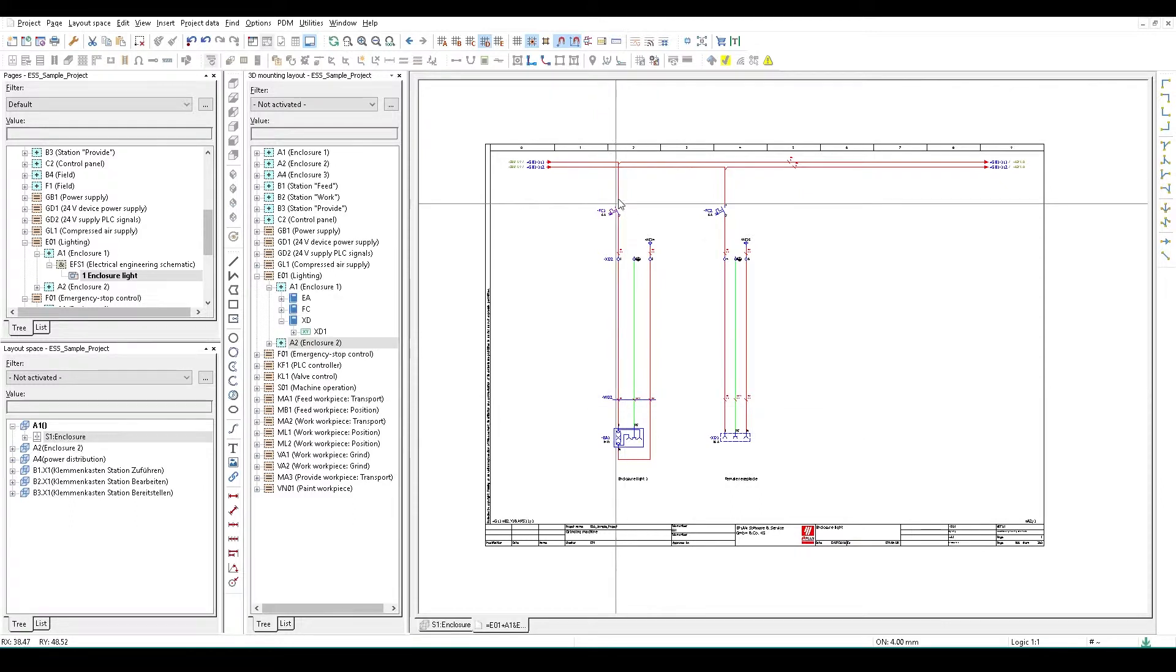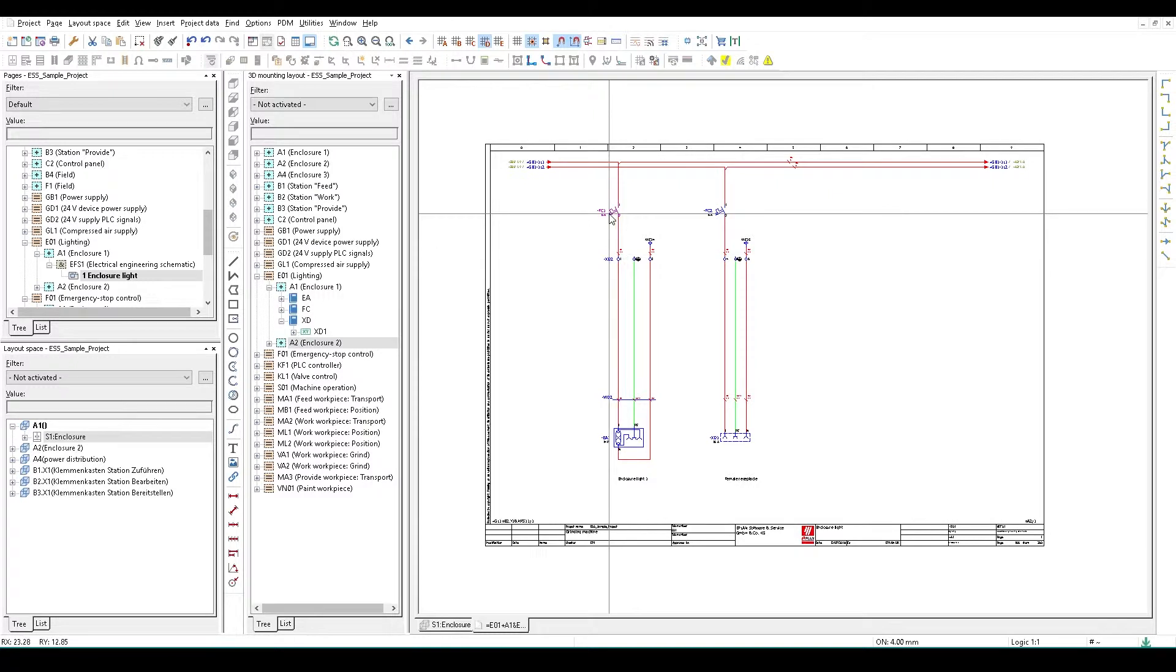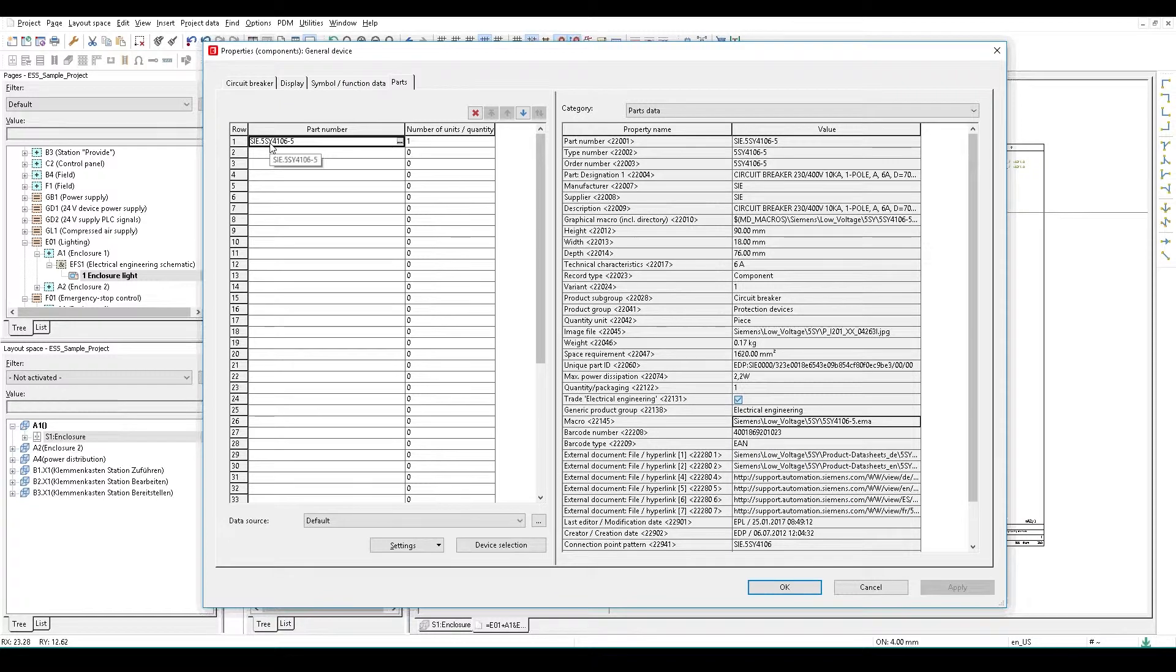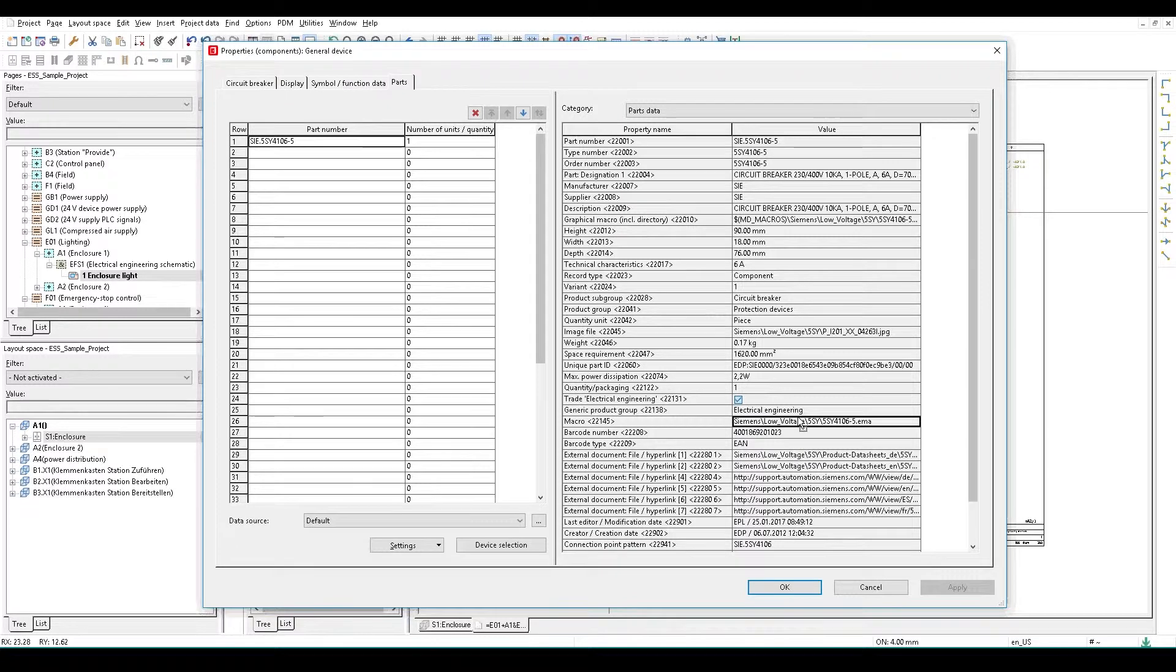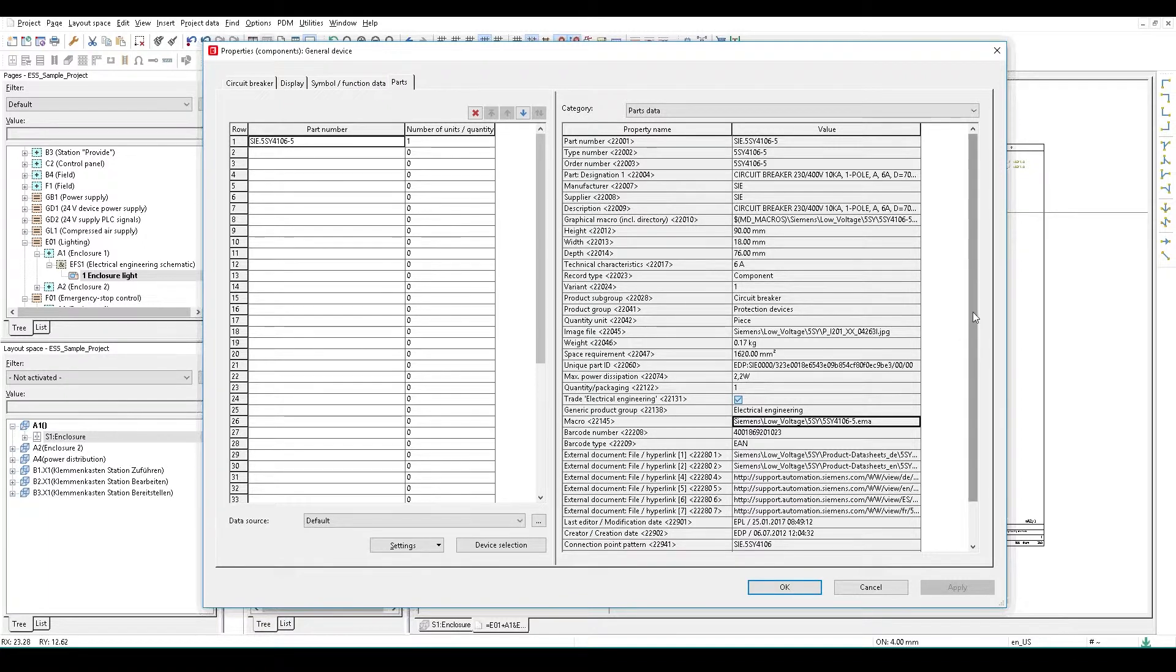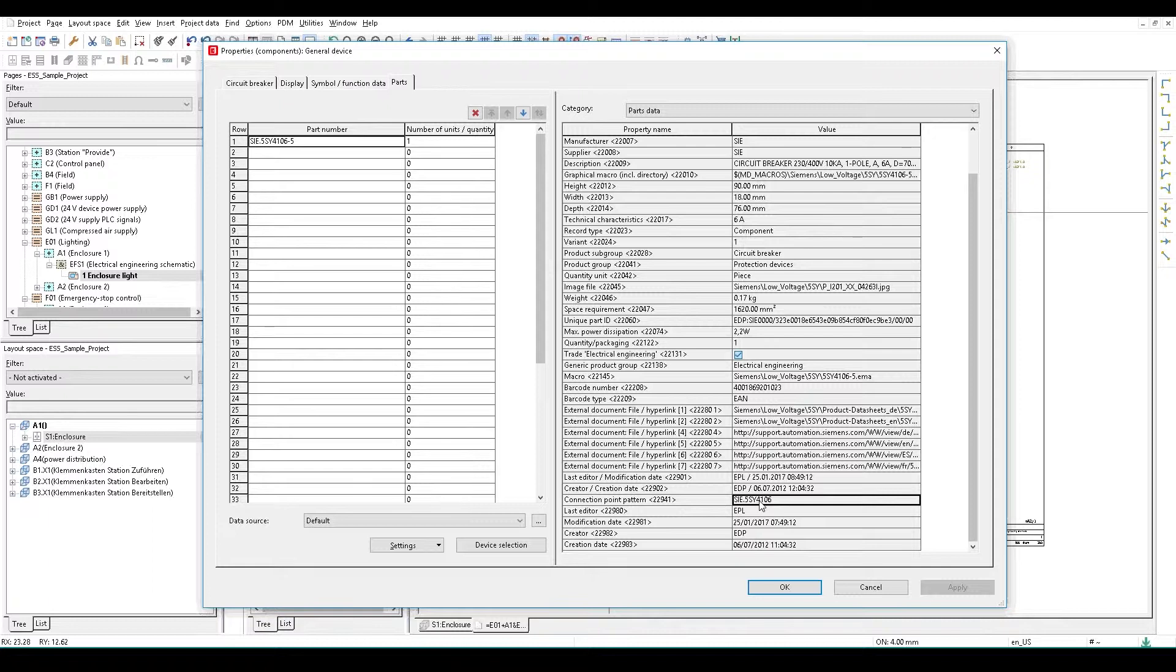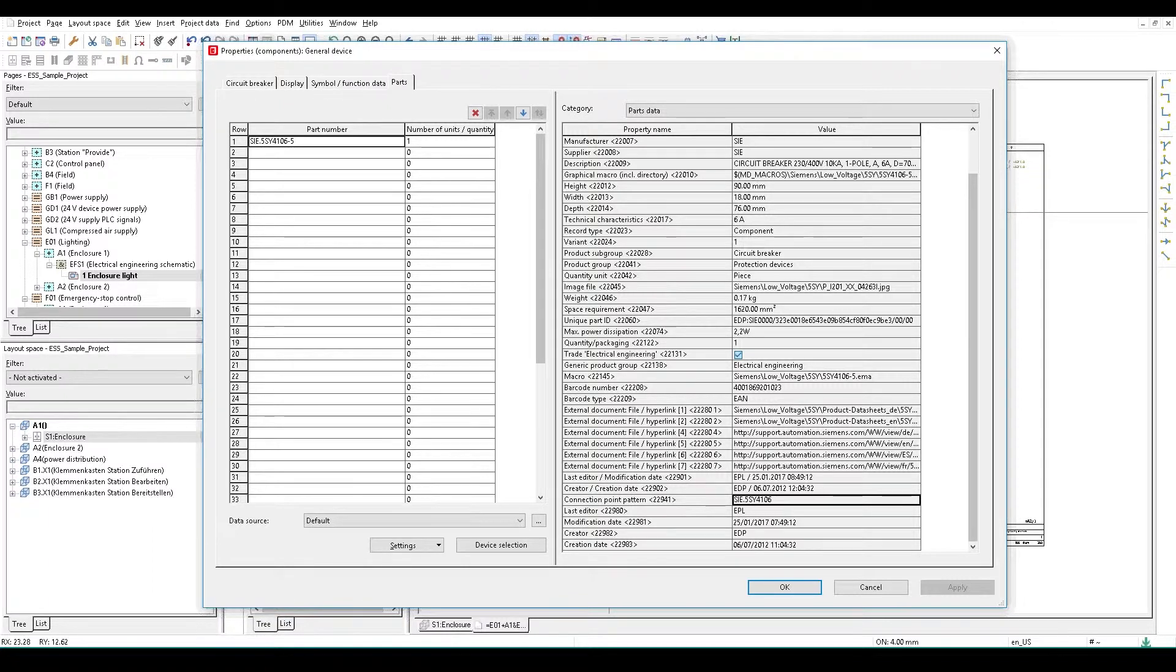But the first thing I'm actually going to do is show you on this particular circuit breaker here. I go to the part number, I can see the part is actually there. I then move over to the right hand side, I can then see things like macros. Macros are going to be able to choose physically what it's actually going to look like inside the 3D world. So they give you the model, give you any connection point pattern, which we can see in here, and how the wires physically get onto that 3D model, and obviously that's going to give us some routing data later as well.